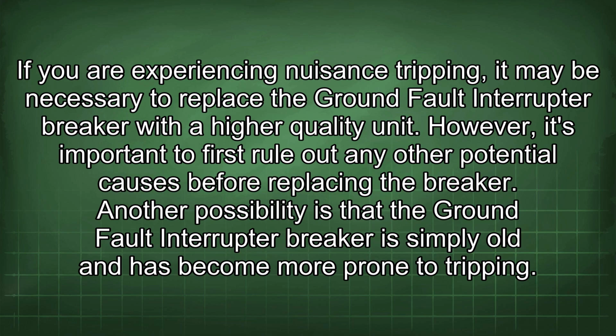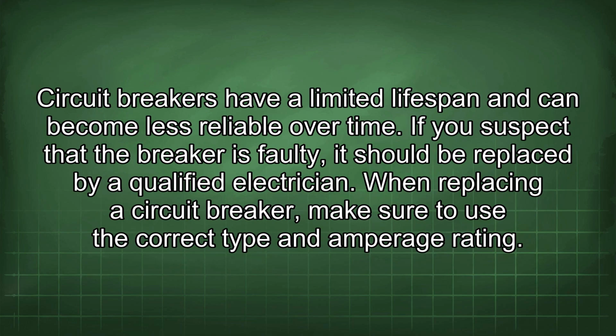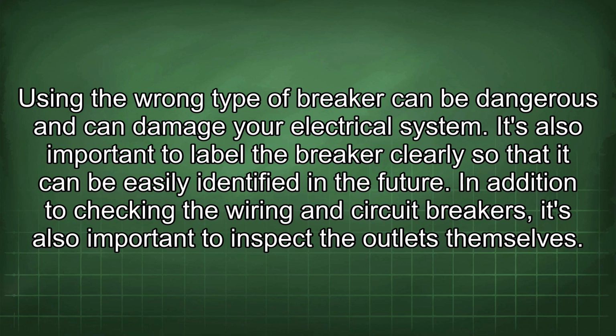Another possibility is that the ground fault interrupter breaker is simply old and has become more prone to tripping. Circuit breakers have a limited lifespan and can become less reliable over time. If you suspect that the breaker is faulty, it should be replaced by a qualified electrician. When replacing a circuit breaker, make sure to use the correct type and amperage rating. Using the wrong type of breaker can be dangerous and can damage your electrical system. It's also important to label the breaker clearly so that it can be easily identified in the future.